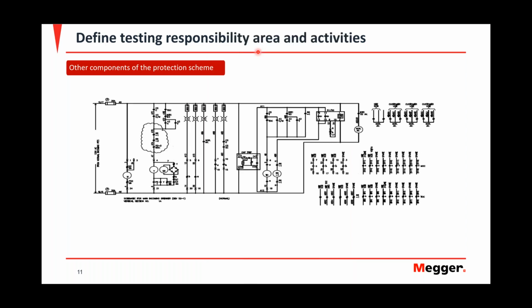Next is defining your testing responsibilities and the area. For this, we're going to make use of this simple three-line. We have a breaker over here feeding a bus, a main breaker. Then you have your CTs right here, some test switches. You've got a relay, a test switch for your voltage, and this is your PT. So we're going to go through this example so we can see the different areas of responsibilities that you could have.